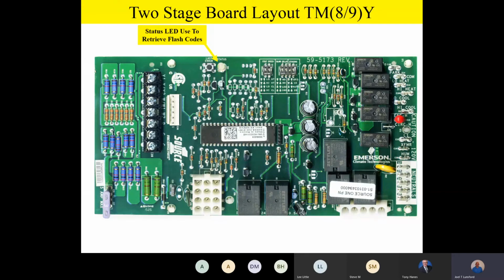Now on this board, we feature some dip switches. On our other boards, you notice we had some physical jumpers. Well, on this board, we have some dip switches. So our continuous fan on speed selection is going to be found with a couple of dip switches. So basically, as you take a look at your photo there, you can see that you've got 2 dip switches that you're going to move up or down, to give you a combination of low heat, low cool, or high cool, continuous fan operation.